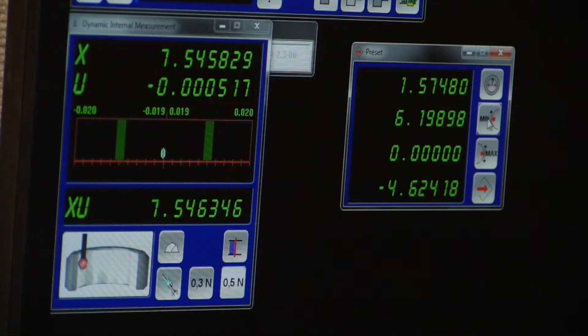We'll bring that into contact here. Get close with the coarse adjustment, lock that, and then tune it in using the fine adjust. Once we have a green check mark on the right side, we can lock in the max measurement.